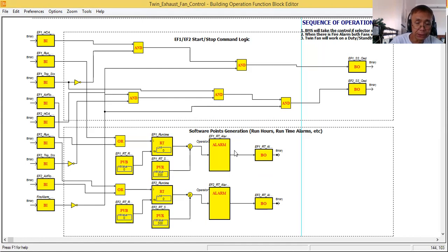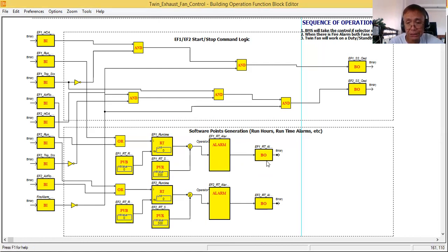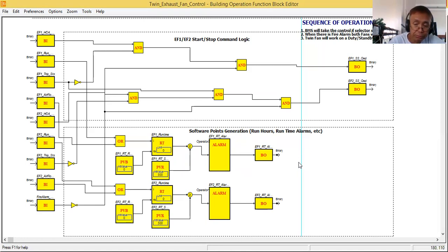When I say physical points, they are associated with or defined in one of the I/O modules used in our DDC. When I say software points — like BO or BI — they are not bound to any I/O modules or the controller; they are just plain software points. You can bind these software points to your BMS graphics.